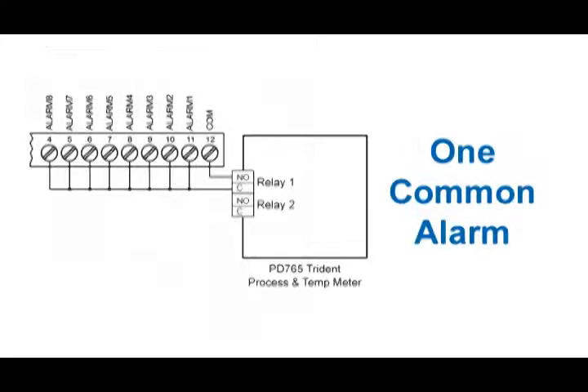Now over here is the more common way, which is what we have in the 178 system, and the PD-765 has two relays, and all we're doing is connecting up one relay to all the alarm in lines. So we have a common set point in this application of 110 degrees, and whenever the Minimux is on a channel that exceeds 110 degrees, an alarm will occur.